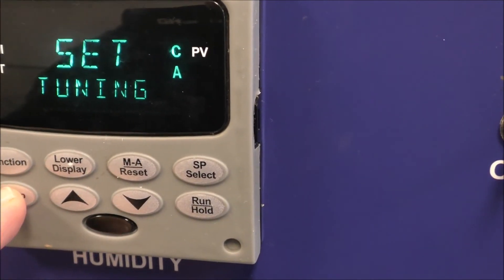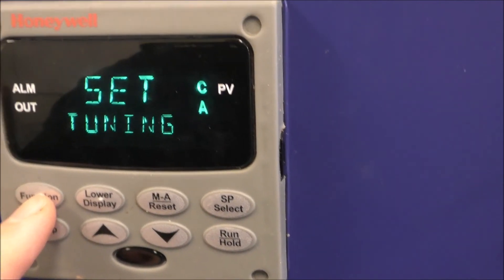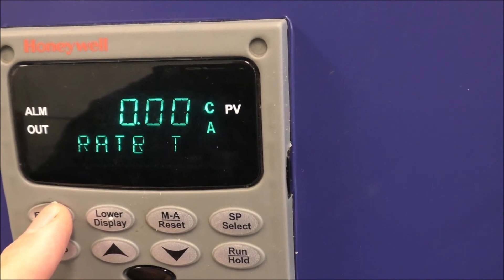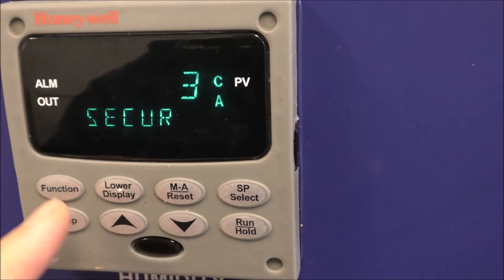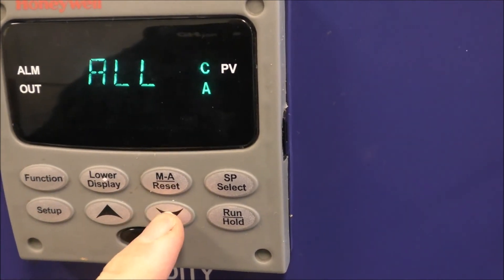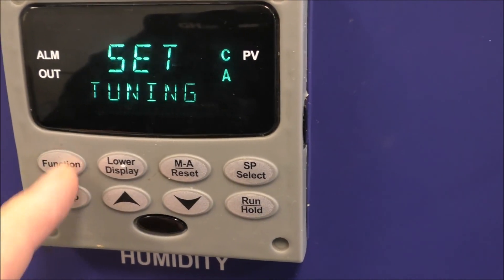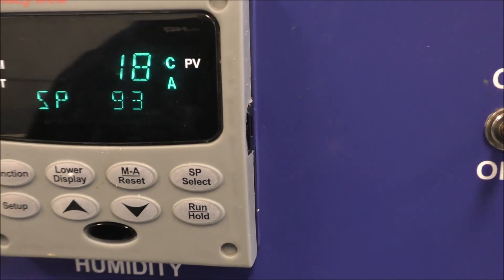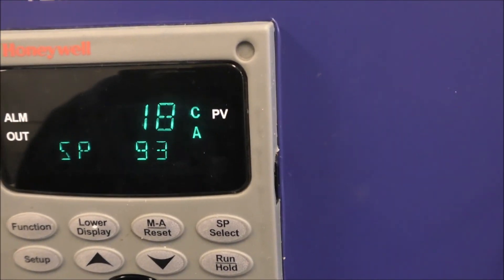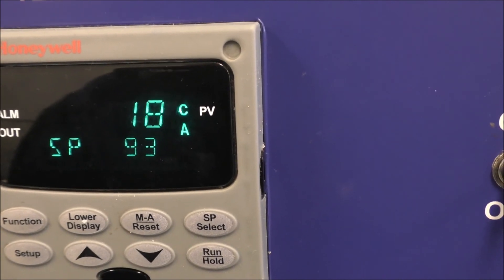Now hit setup again, go back into tuning, go into pushing the function button, go back to security, push the arrow until you hit three, function again, push the down arrow once so it says all, hit function again, and then hit lower display. Once you've done all that, the unit will read and display in Celsius.